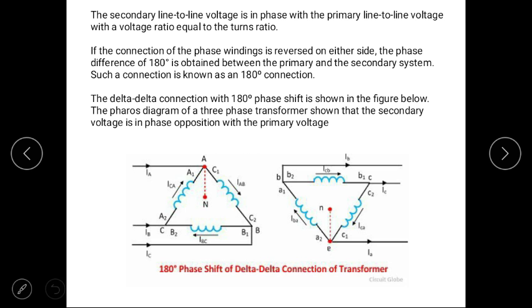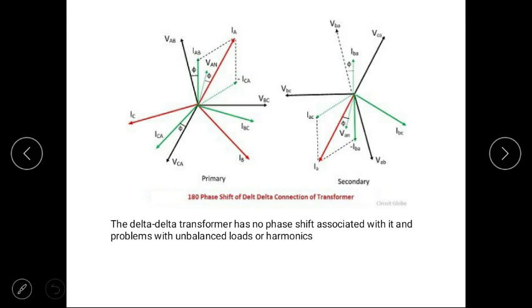The secondary line-to-line voltage is in phase with the primary line-to-line voltage, with a voltage ratio equal to the turns ratio. If the connection of phase winding is reversed on either side, a phase difference of 180 degrees is obtained between the primary and secondary system; such a connection is known as the 180-degree connection. The phasor diagram of a three-phase transformer shows that the secondary voltage is in phase opposition with the primary voltage after this phase shift.